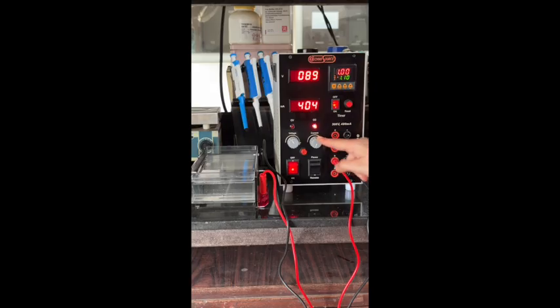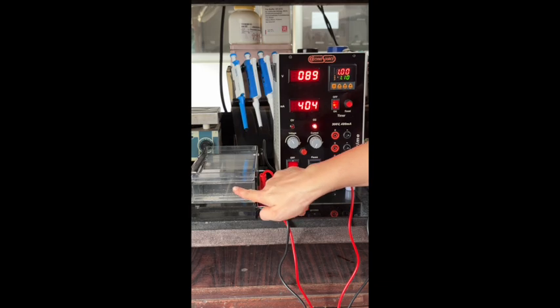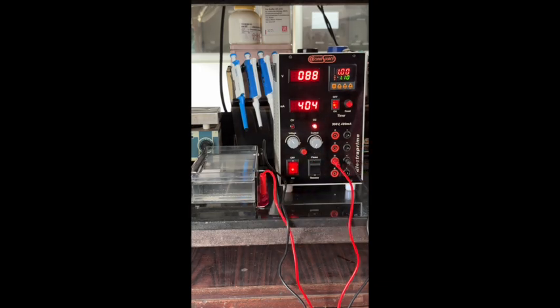Make sure the current knob is turned fully clockwise. If yes, then check the buffer level and the buffer composition. If both are correct, then you will need another power supply with higher current ratings. You can check our website link.